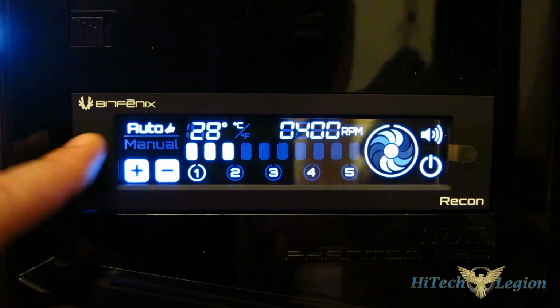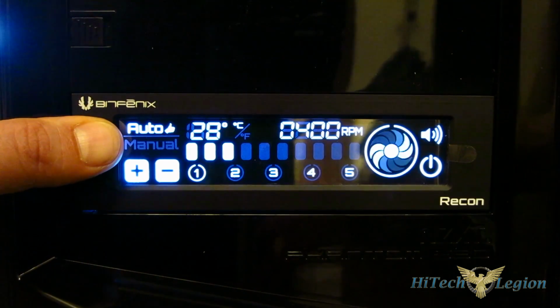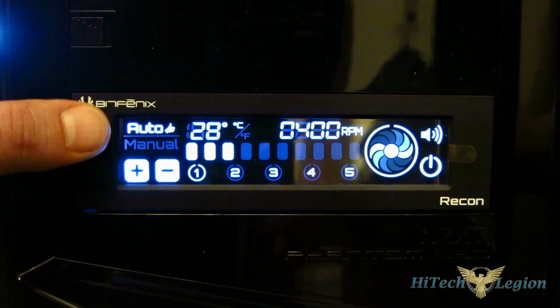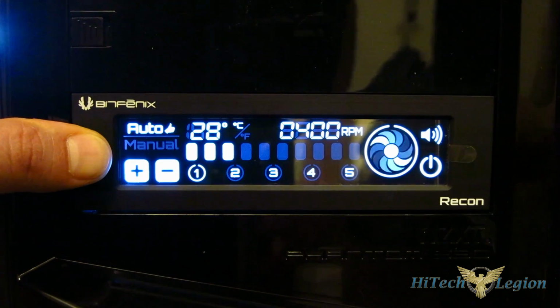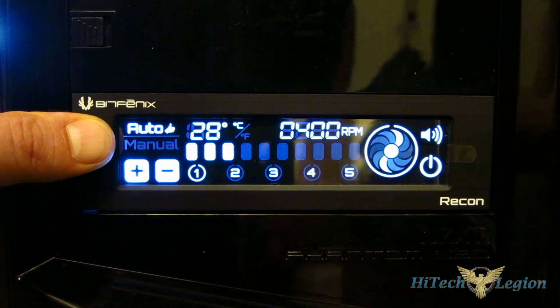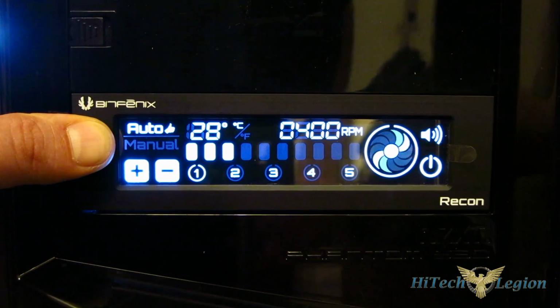You see it's in auto mode. In auto mode, you're going to be at 40% fan speed at 20 degrees centigrade, and it's going to ramp up to 100% at 60 degrees, and anything above 60 is going to stay at 100%.